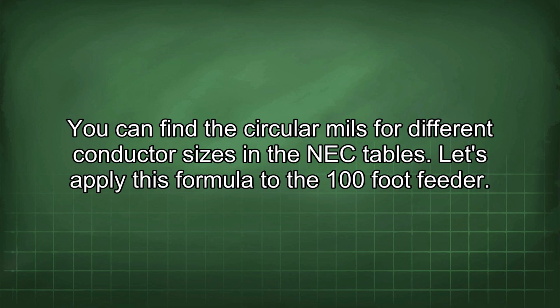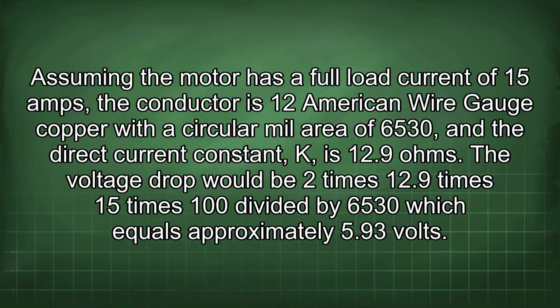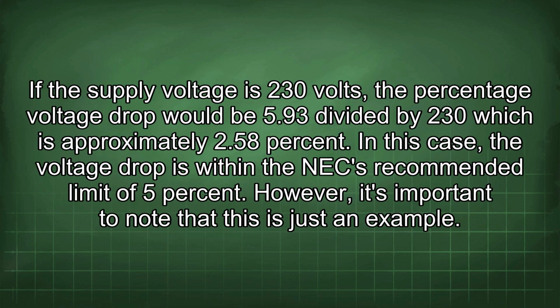Let's apply this formula to the 100-foot feeder. Assuming the motor has a full load current of 15 amps, the conductor is 12 American wire gauge copper with a circular mil area of 6,530, and the direct current constant K is 12.9 ohms. The voltage drop would be 2 times 12.9 times 15 times 100 divided by 6,530, which equals approximately 5.93 volts. If the supply voltage is 230 volts, the percentage voltage drop would be 5.93 divided by 230, which is approximately 2.58%. In this case, the voltage drop is within the NEC recommended limit of 5%.